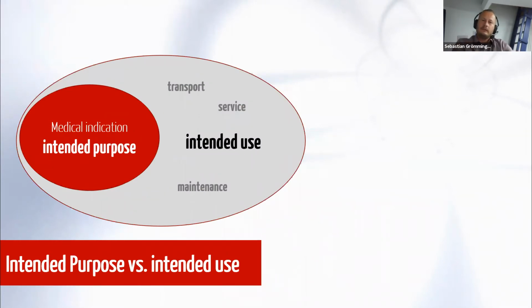So it's necessary to know that the intended purpose is part of the intended use, but the intended use is not only the medical indication, it is as well additional scenarios like transport scenarios. Service and maintenance are very frequent intended uses, additional use scenarios that are necessary for the medical device to perform accordingly and be compliant, to stay compliant within the market.